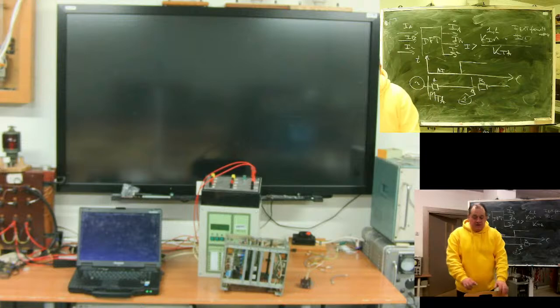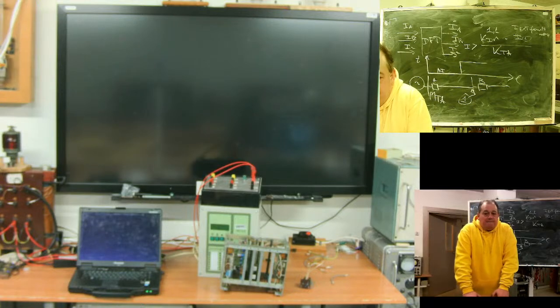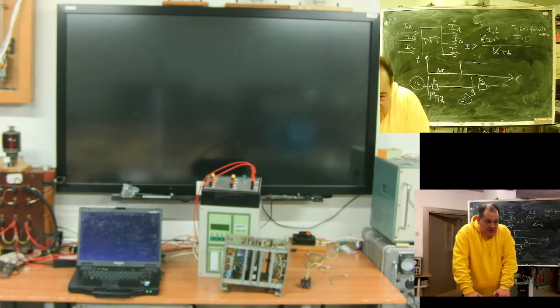Can protection operate absolutely instantly? What's your knowledge in power system protection? Lightning, surge arresters. You cannot operate absolutely instantly. Anyway, you need a short delay, 50 milliseconds or 100 milliseconds. Why? Because you have surge arresters, lightning protection on your line. In case you get a lightning strike, surge arresters open, we need to give them time to operate.